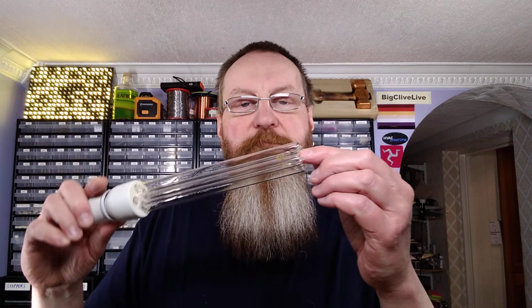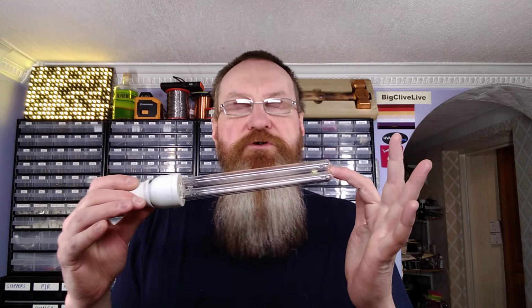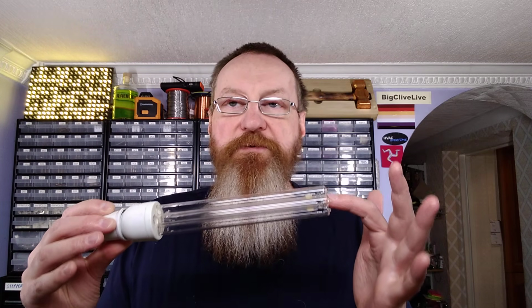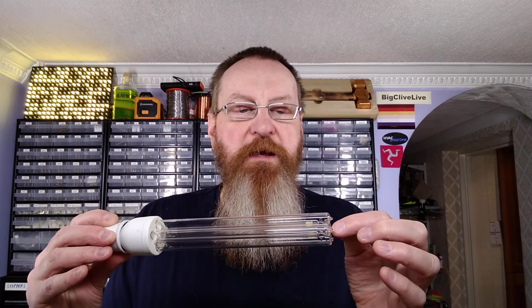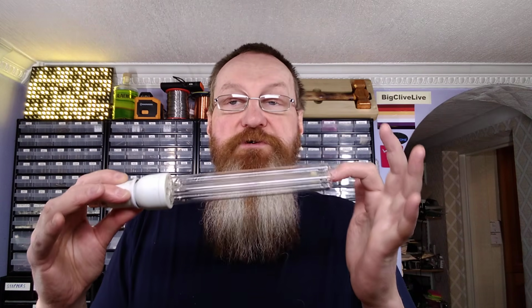So one of the ways to create ozone is using an ultraviolet lamp, and this is popular in catering industry ozone generators. So this is a UVC lamp, and it produces two wavelengths. Now, an ordinary germicidal lamp would just produce 254 nanometer UVC. But the ozone-producing lamps have a much purer glass, and it passes another wavelength of the mercury vapor discharge inside at 184 nanometer.